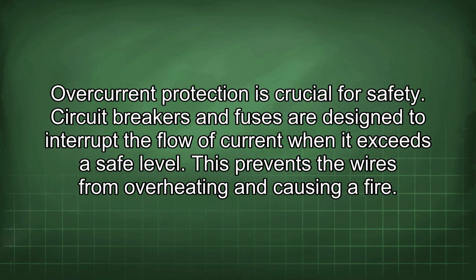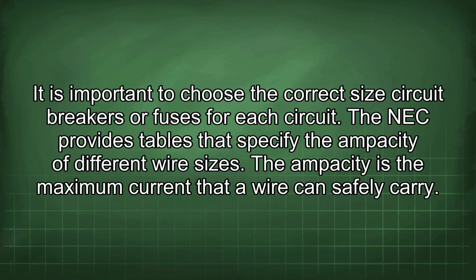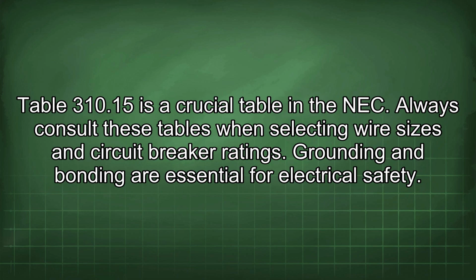Overcurrent protection is crucial for safety. Circuit breakers and fuses are designed to interrupt the flow of current when it exceeds a safe level. This prevents the wires from overheating and causing a fire. It is important to choose the correct size circuit breakers or fuses for each circuit. The NEC provides tables that specify the ampacity of different wire sizes. The ampacity is the maximum current that a wire can safely carry. Table 310.15 is a crucial table in the NEC. Always consult these tables when selecting wire sizes and circuit breaker ratings.